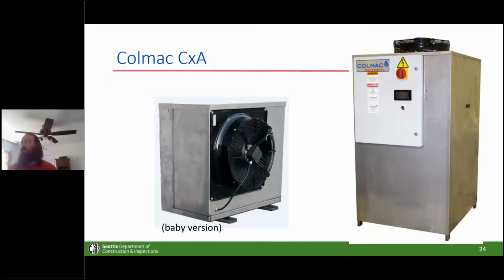Well, I just wanted to add that if you're up against a storage capacity issue, remember it's BTUs that you're trying to store. So you could store your hot water at a very high temperature, and then it's running through a mixing valve anyway. But be aware that we have a requirement that if you do store at higher temperatures, you have to add more insulation on your tank.